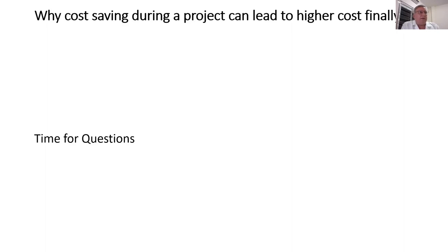And also, what I mentioned, especially with Delta V, this alarm help. I'm not sure you used that. I cannot remember. But you click on it and get a text which you can edit yourself as a customer, and you don't need to program this. You can open it, and with the right access, just type in what the operator has to do in this moment. The system can help you, but analysis is something you need to do later, when something happened and you want to know why. Then the system should give you at least all the data. It should tell you what the reason was, what the first alarm was and all of this, and you get it from your log events, so you can trace that. But for better analysis, you need your external programs. I think no other way.